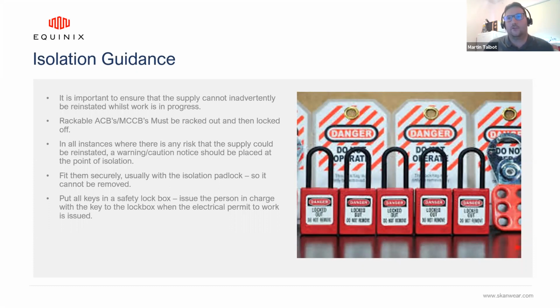We need a good system of applying safety locks and good control of keys, accounting for who's applying for keys, where the keys are held, who's got them, and things like that. We shouldn't be using safety locks for decommissioned circuits, in my opinion. Safety locks are there for when isolations and work are being carried out. If you go along any switchboard, the only time you should see a safety lock in place is when work is being conducted. If you've got decommissioned circuits being effectively decommissioned by a safety lock, I don't believe that's right. That circuit should be pulled back from the circuit breaker or isolation device, so it can no longer be connected, and then the safety lock can be removed.